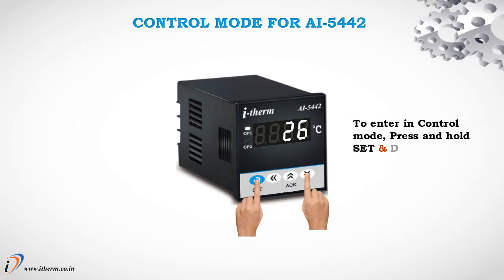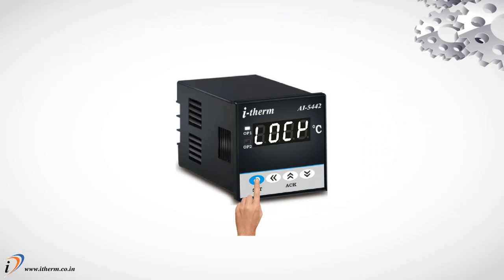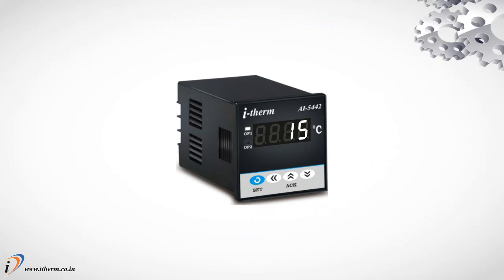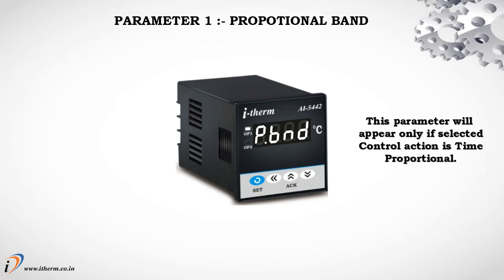Control mode for AI5442. To enter in control mode, press and hold Set and Down key simultaneously for 3 seconds. Set this parameter to 15 to access control list. Parameter 1. Proportional band. This parameter will appear only if selected control action is time proportional.